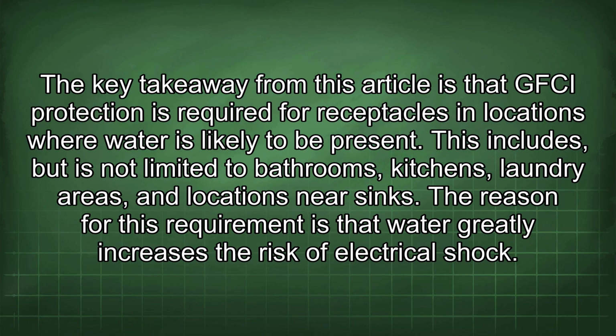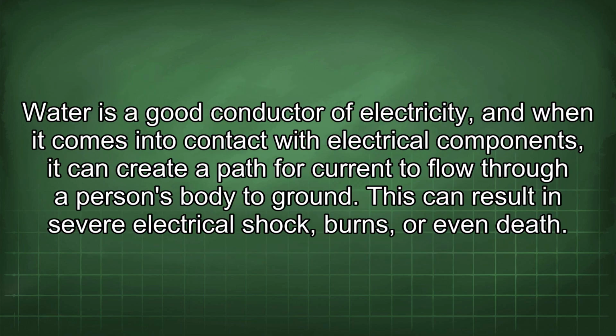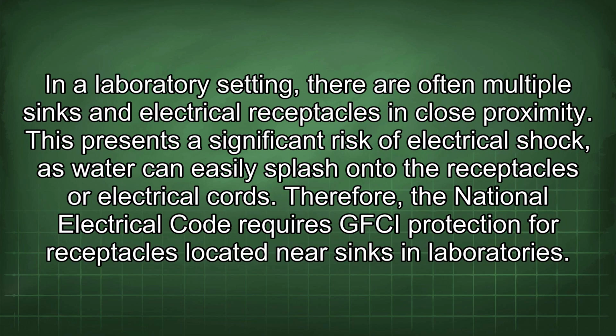The reason for this requirement is that water greatly increases the risk of electrical shock. Water is a good conductor of electricity, and when it comes into contact with electrical components, it can create a path for current to flow through a person's body to ground. This can result in severe electrical shock, burns, or even death. In a laboratory setting, there are often multiple sinks and electrical receptacles in close proximity. This presents a significant risk of electrical shock, as water can easily splash onto the receptacles or electrical cords. Therefore, the National Electrical Code requires GFCI protection for receptacles located near sinks in laboratories.